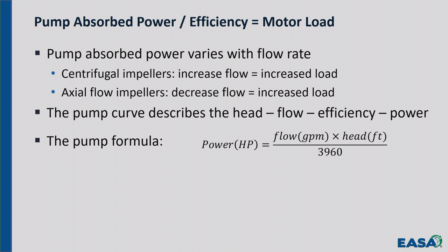And if you recognize that and can look at the pump curve and talk to your customer about, well, what's the head and what's the flow? A lot of conversations stop right there, because if you ask your customer, you said the motor's pulling high current, so what's the head on the pump and what's the flow? Do you have a copy of the pump curve? My problem just ended, because he doesn't have the pump curve and he doesn't know the numbers. And I'm not being mean here to the gentleman, but that's the fact. I mean, if you don't know the head and you don't know the flow and you don't have a pump curve and the motor's pulling high current, it's not my problem yet. Okay? You have to get that information, and then we can work on why we have the high current.